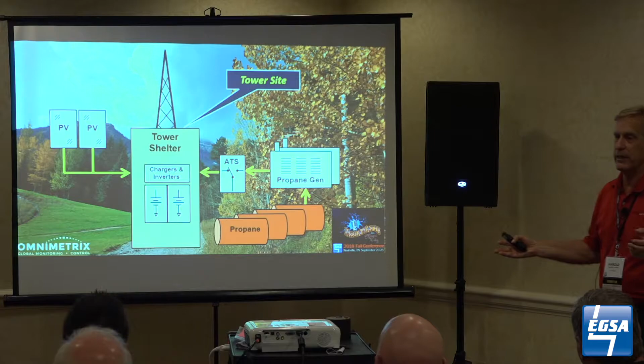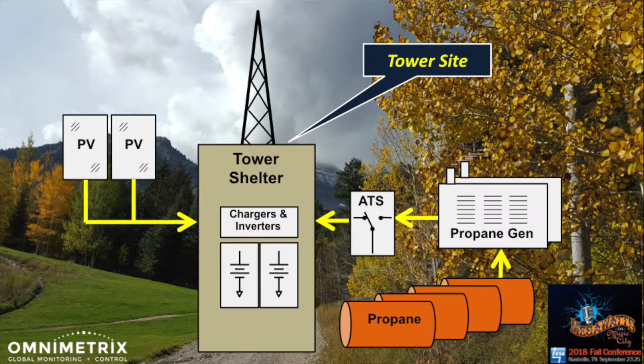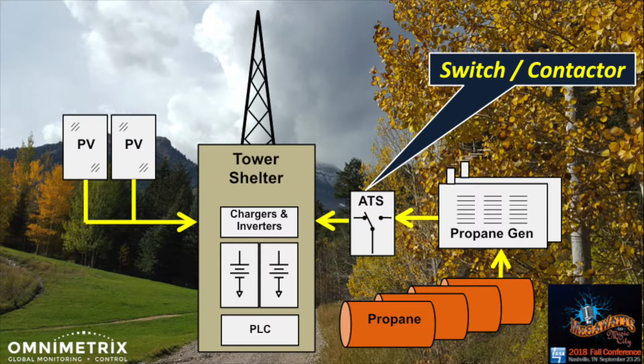Schematically, they're using both photovoltaics charging the battery system as well as generators, and they're using propane, with multiple tanks, which makes that step of gauging interesting. So 10 kW of photovoltaics, 30 kW generators, and in some cases they use a single, in some cases they have alternating. I'll show you an alternating one here in a sec. There's the fuel supply and the transfer switch or contactor, because among the other things here is the PLC that runs the site. That PLC is the subsystem that has to determine: do I have to run my generator because I didn't get enough sun today? So it's really in control of the site.